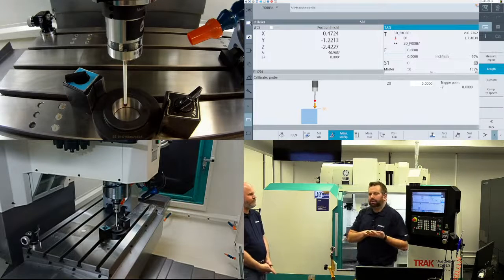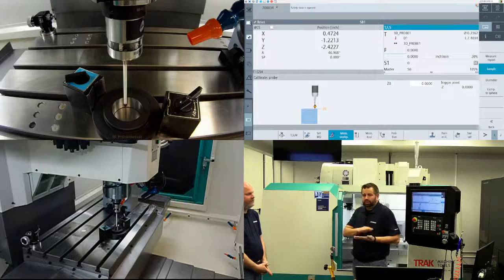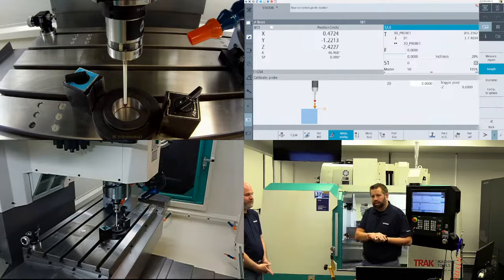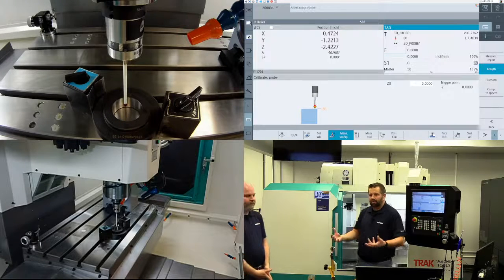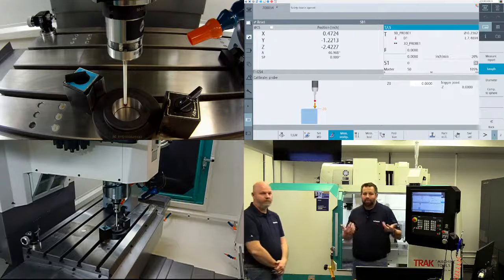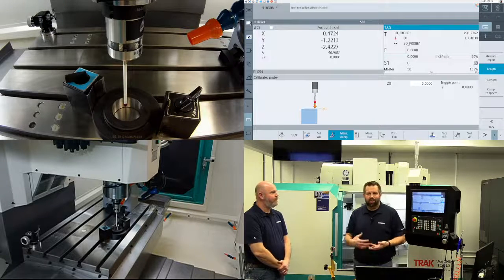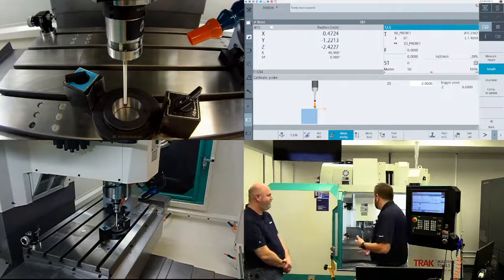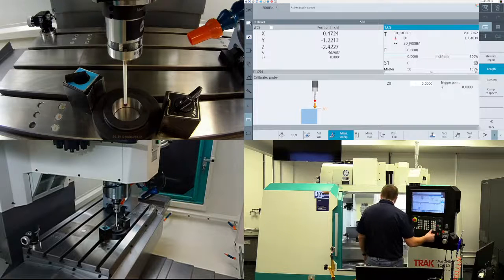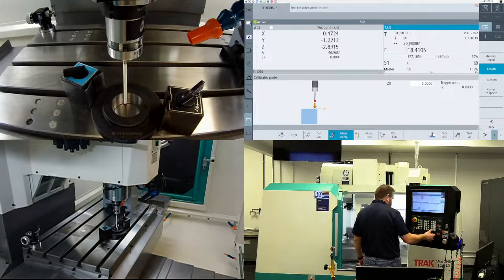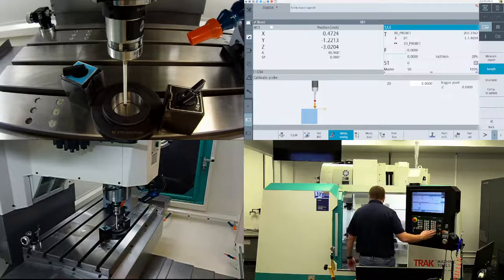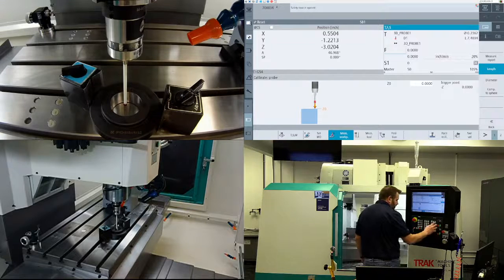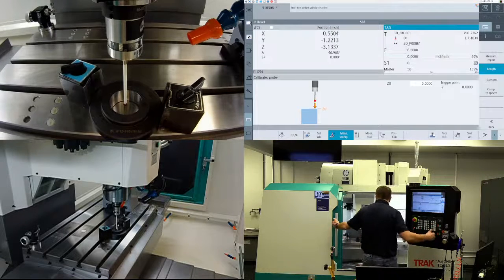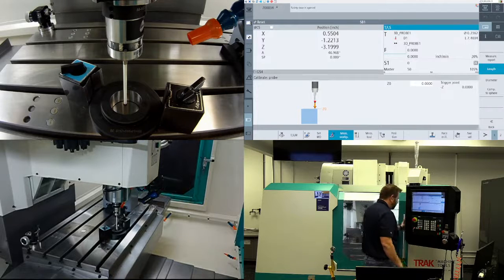We know this is a measured artifact to the diameter that's written on the ring gauge, so that's what's given to you. If you don't have a ring gauge, make your own, but make sure you have the proper ways of validating what that diameter would be. Yeah, I think we've all done the crude method just to get a jam to get things going in the past. But I would absolutely agree. Long term, you have to go off of a qualified artifact.